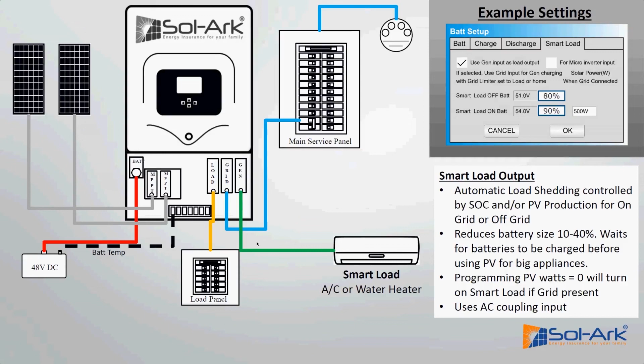A lot of times folks start out with a smaller battery bank than they really needed, because batteries can be a fairly substantial chunk of the cost of an install. So they want to know how long they have to add more batteries. It really depends on the chemistry. For lead acid, you have about a year to add more batteries without it being too detrimental. For lithium, as long as it has a BMS, you can pretty much add one whenever, because the BMS will handle the differences between the cells hooked up in parallel.